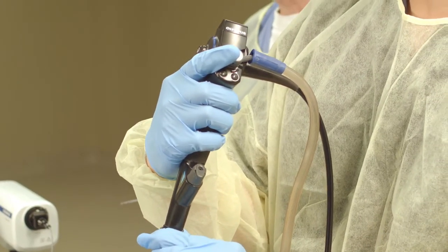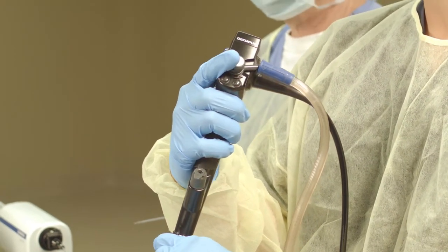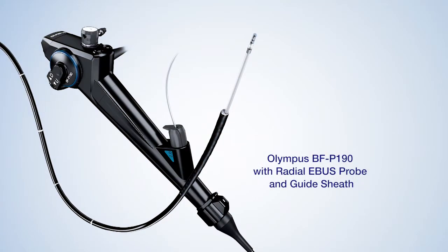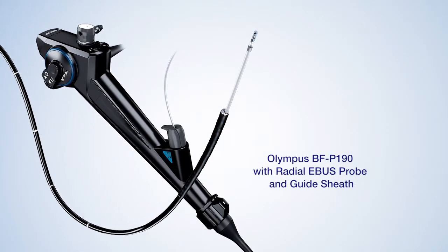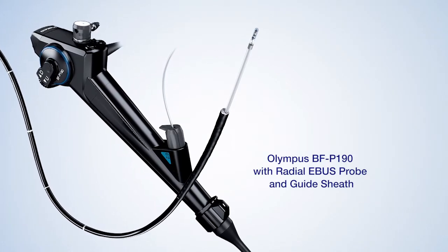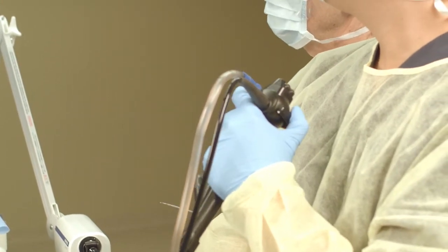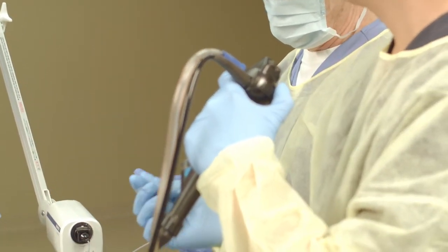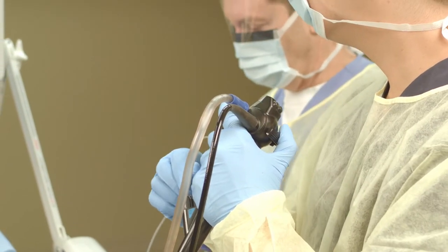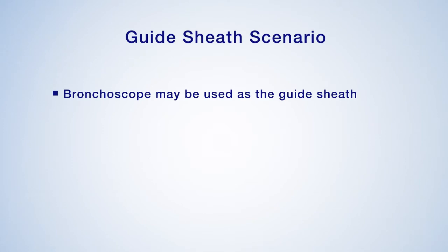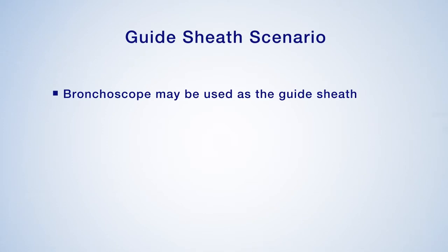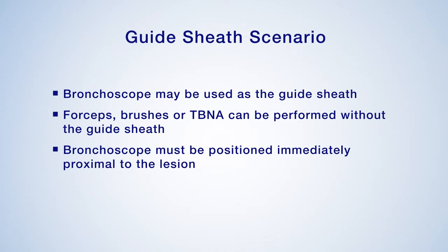Smaller caliber bronchoscopes, such as the 4.2-millimeter outer diameter BFP190, allow improved accessibility to the lung periphery such that the bronchoscope may be advanced all the way to or in close proximity to pulmonary nodules. The bronchoscopist may choose to use the guide sheath kit in this scenario or may forego the guide sheath if the bronchoscope closely approximates the pulmonary nodule. In this scenario, the bronchoscope may be used as the guide sheath and forceps, brushes, or transbronchial needle aspiration without the guide sheath can be performed with the bronchoscope positioned immediately proximal to the peripheral lesion.